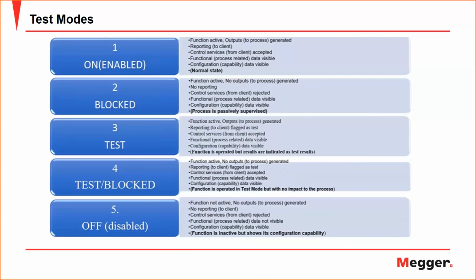And this is not something you can only do for the whole IED itself, but you can do it for each logical node. So each protection function, I can put it in test mode. I can put only the distance overcurrent, for example, or only the differential protection in my IED, or even only a certain small node of that whole function. So only distance zone 1, for example, I can put it in test mode in some relays to that level.